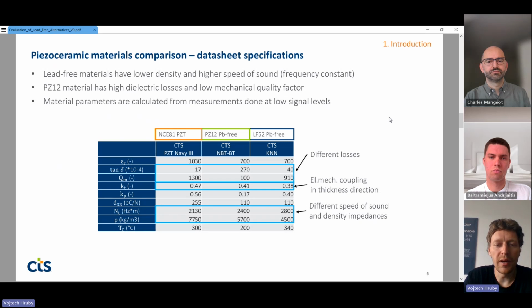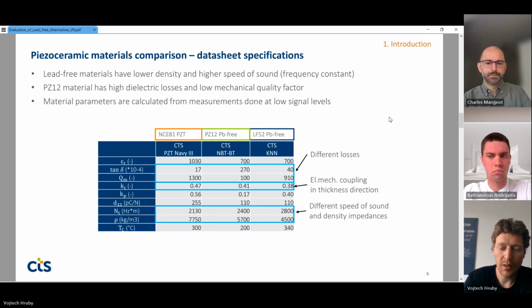If we look into selected parameters of the piezoceramic materials we tested in this study, we see that PZ12 material has much higher losses, that is the tangent delta and mechanical quality factor. Also, if we look into the acoustical properties of materials, we see that both lead-free materials have a much higher speed of sound and a lower density than PZT material. So that affects some behavior of the transducer.